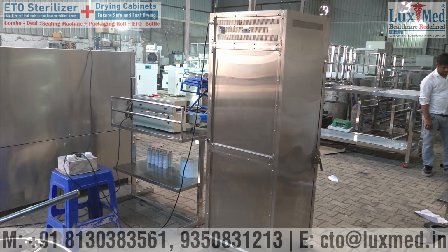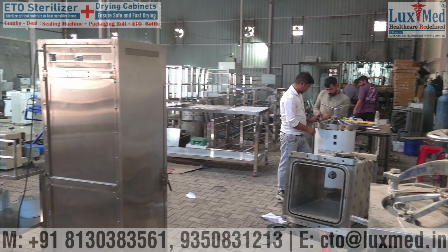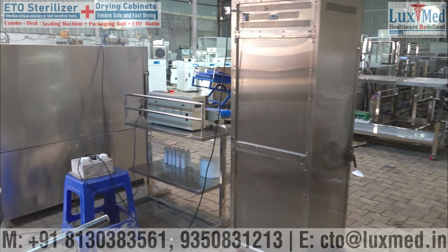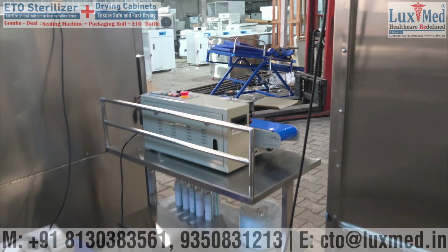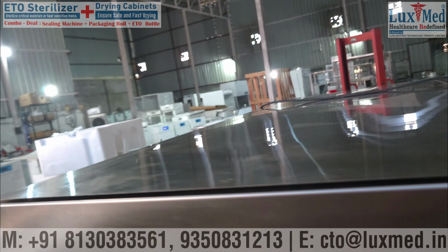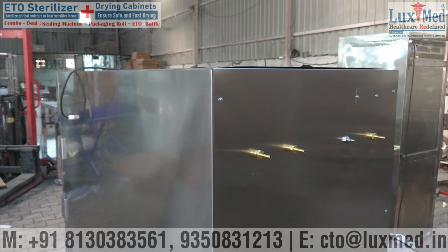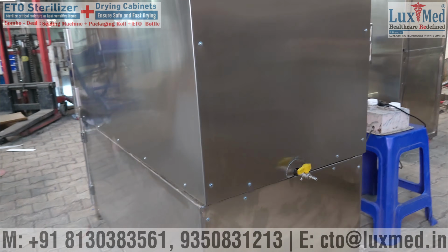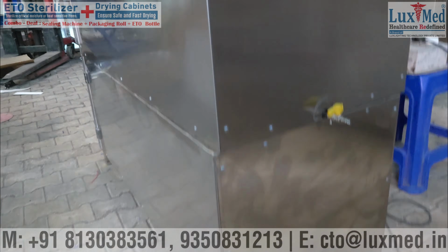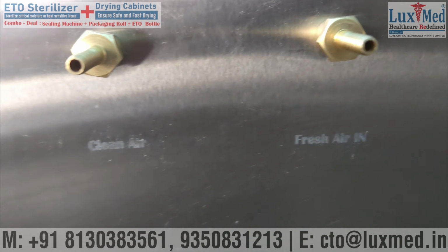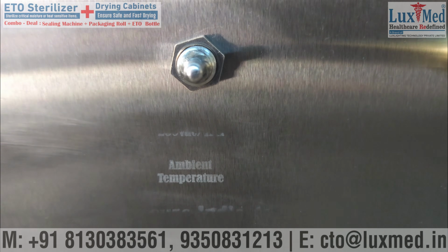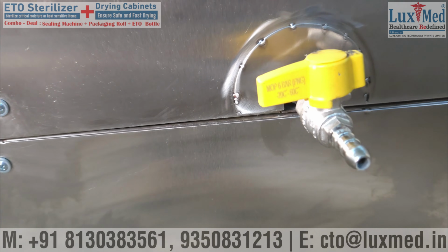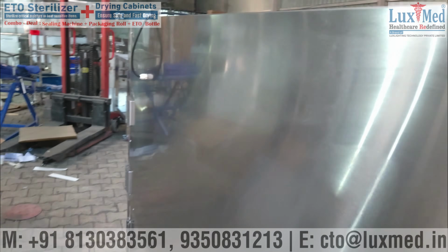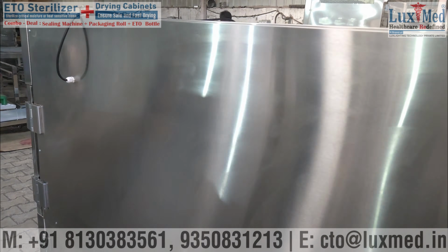Drying cabinet. Also known as a medical dryer or drying oven, this unit is primarily used to dry large volumes of medical instruments, tubes, and labware before they undergo sterilization. Mechanism: uses a forced hot air circulation system that controls heat loss and ensures items are completely bone dry. Application: prevents the growth of waterborne bacteria and ensures that residual moisture does not interfere with the efficacy of sterilization processes like ETO or steam. Key features: features HEPA-filtered air intakes, adjustable temperature settings, high, medium, low, and modular racks for different instrument sizes.